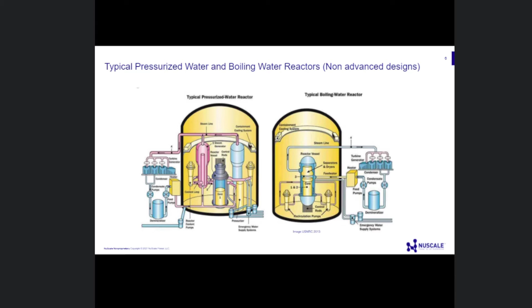Both types of plants have lots of pumps on the outside, high pressure and low pressure fill pumps, safety injection pumps, and core cooling pumps that on some plants spray water right into the top of the reactor. All of that stuff has nothing to do with making power, they're all huge pumps, 480 or larger motors, usually 50 to 2,000 horsepower, and their only job is to sit there in case of an accident. Both plants are very similar for that. Boiling water plants have stuff inside their containment that does other things, but we're not going to get into those differences, it's just way too long. Okay, move on to the next slide.